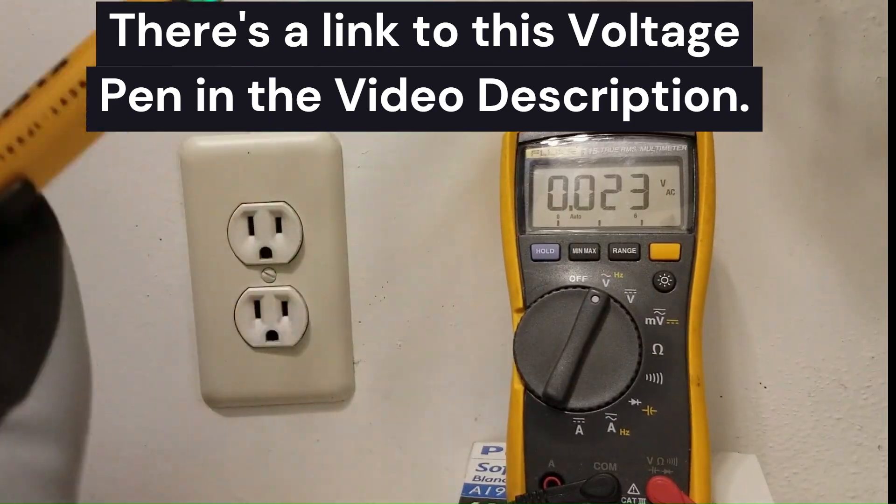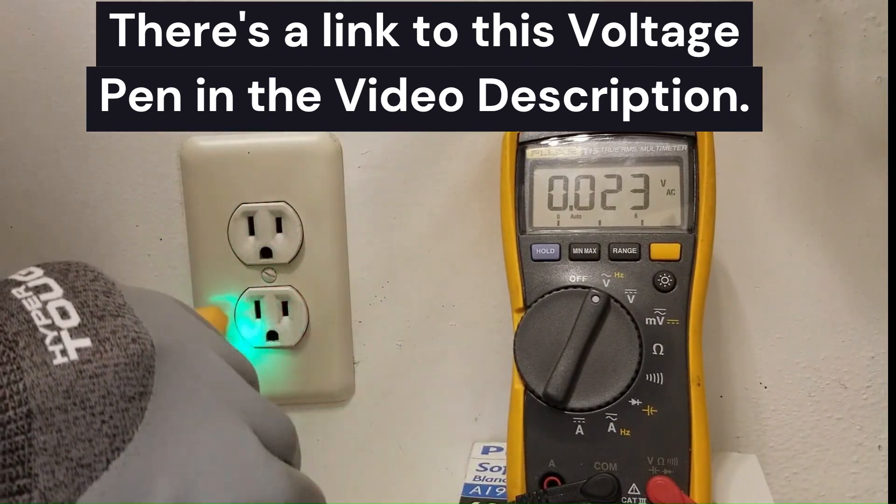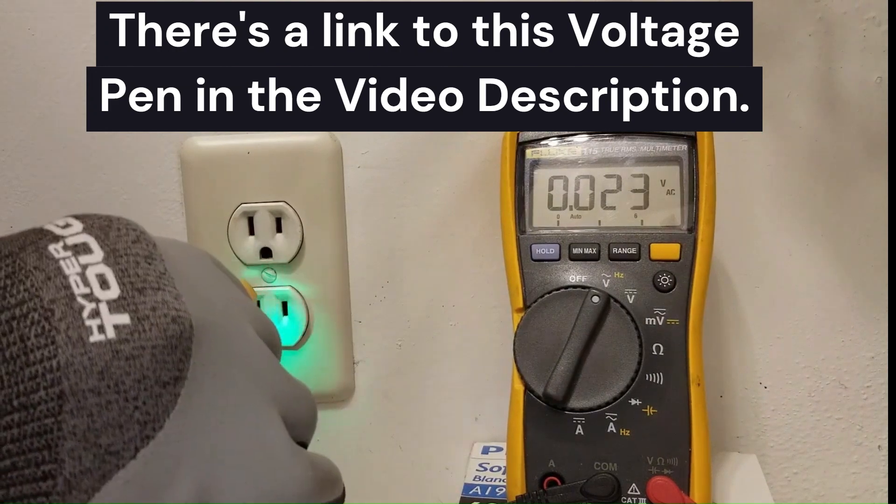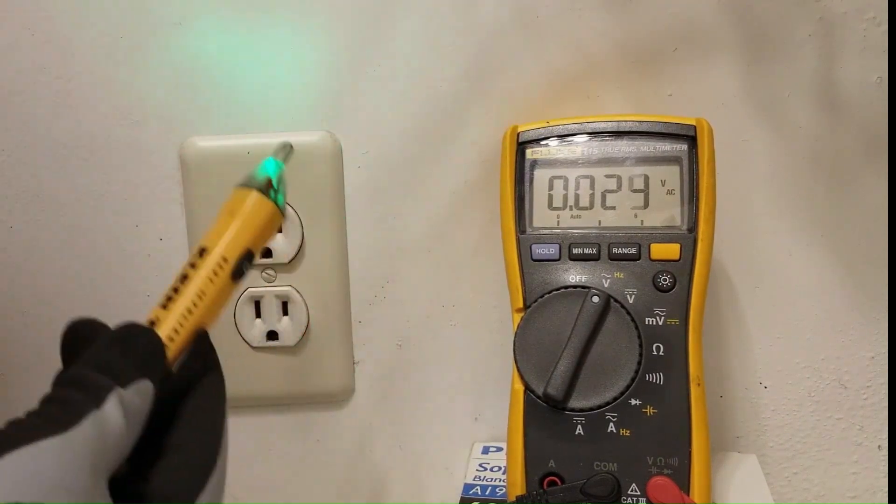So that's a really good way a voltage pen can tell you if you have a loose upstream neutral with respect to this outlet that is causing this outlet to fail under load.